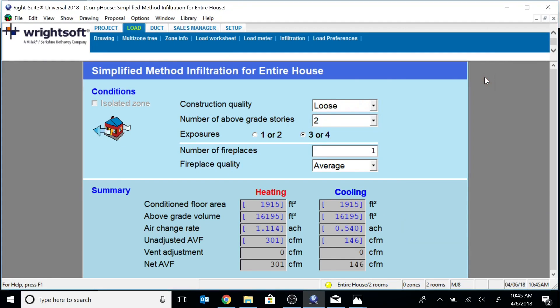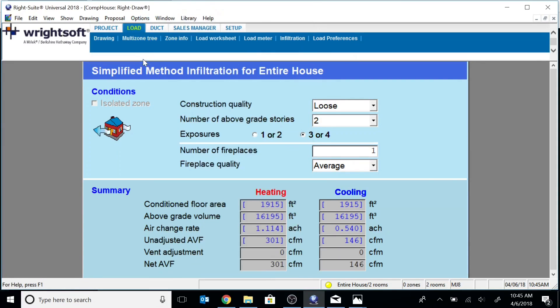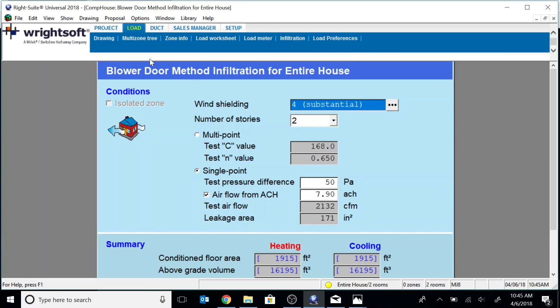I'm at 7.9 ACH50 — so it's pretty good. 1915 square feet, 2132 CFM. Pretty good.